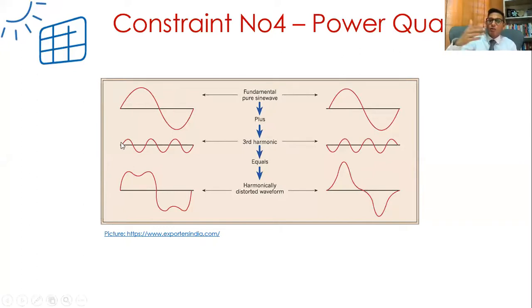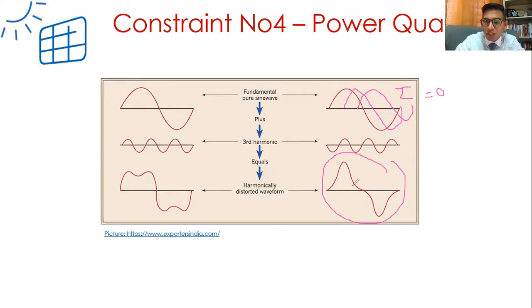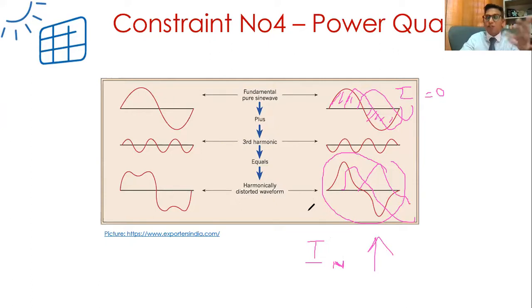Even your lights contribute: incandescent lamps have been replaced by CFL and LED lamps, but LED is powered by DC, adding more harmonics. Harmonics have a whole array of disadvantages. In a balanced three-phase system, the neutral current should be zero as the three phases cancel each other. But with harmonically distorted waveforms, they don't cancel, so neutral current becomes very high. Since the neutral conductor is normally sized for balanced load, this high neutral current causes heating, which can cause fire. One new source of harmonics is PV as well as wind - wind turbines have power electronic drives that are also electronic devices.